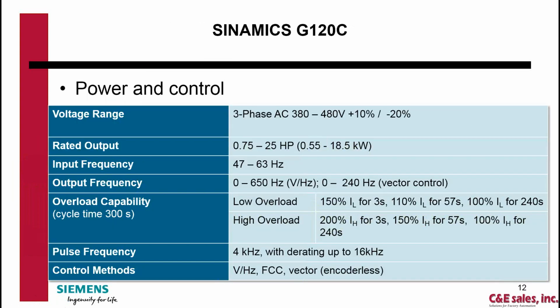Here's the big difference with the C: it's pretty much limited in range. 380 to 480 volts, 3-phase, 3/4 to 25 horsepower. Again, the G120 and G120C can do the volts hertz type control, but also your open loop vector control. And then the CU250 we talked about can do the closed loop vector.